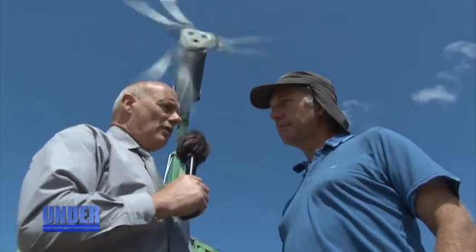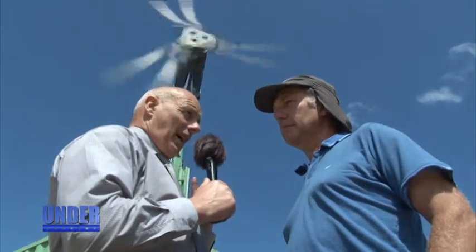So that brings me to the question of what happens to the electricity that's generated up there? How is it circulated around the house or around the farm? What happens is this feeds directly through a synchronous inverter onto any distribution board anywhere on your system. So your system will always take whatever the turbine is producing first. If you're producing more than you're using, the surplus feeds back onto the grid and the power company buy that off you. If you're producing less than you need, you'll take whatever the turbine's producing or solar, and it will seamlessly top up from the grid. So there's no switching between one another. You have no idea whether the power is off the turbine or off the grid. You just get constant full power all the time.